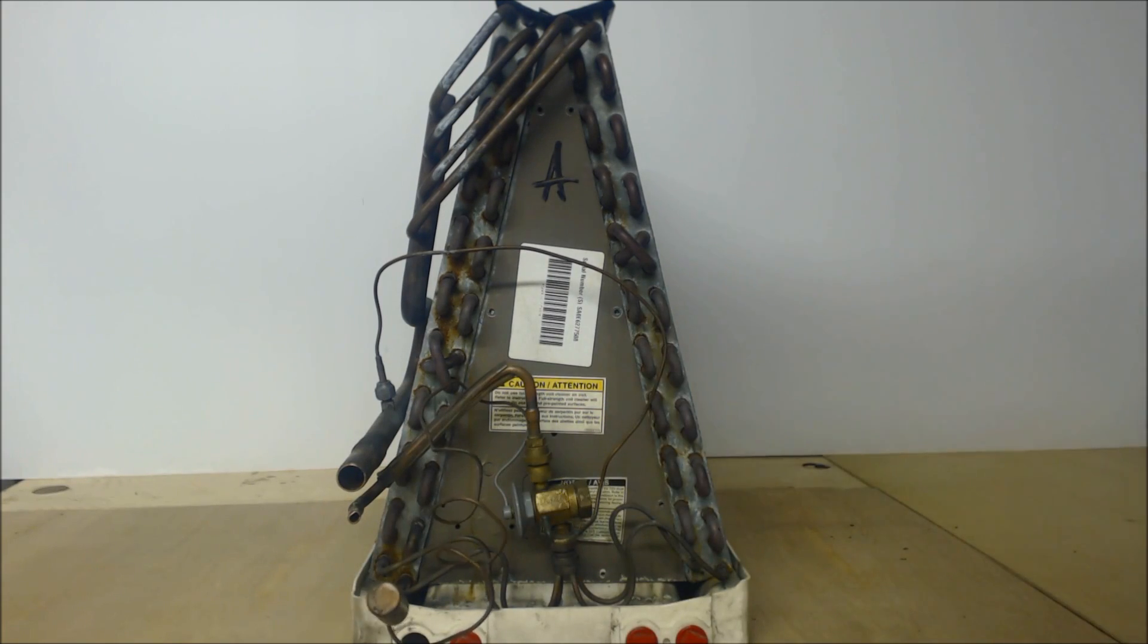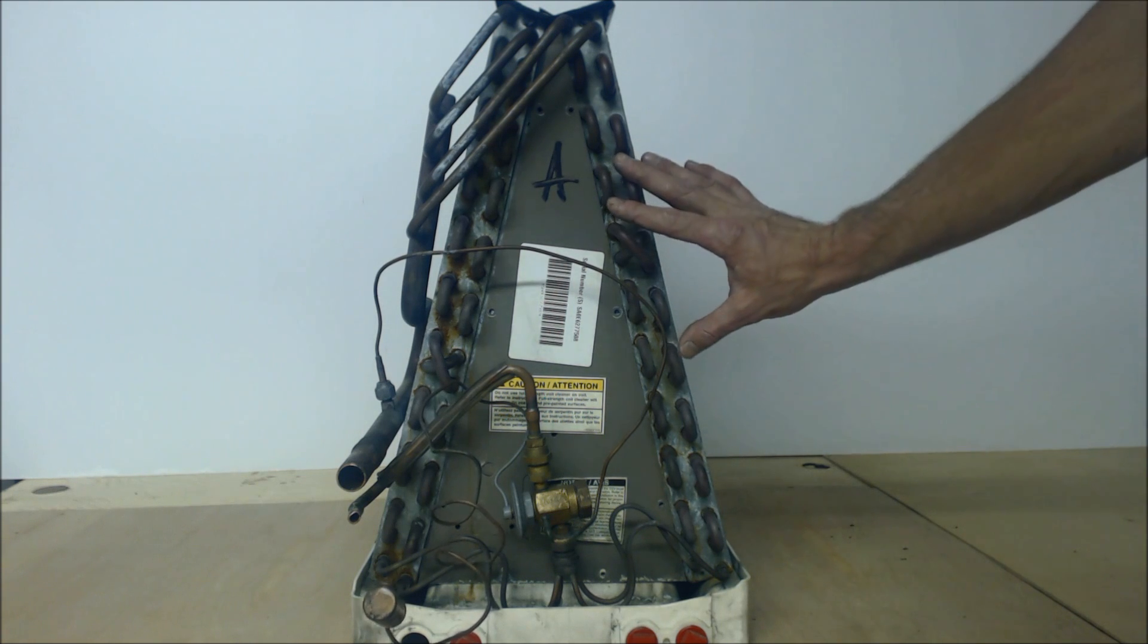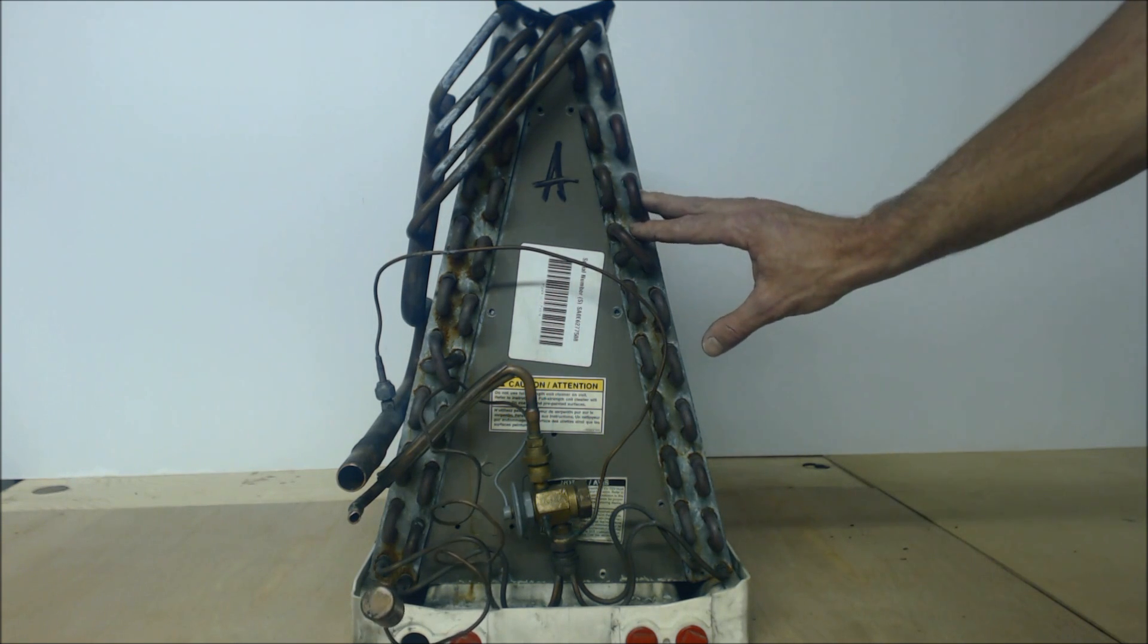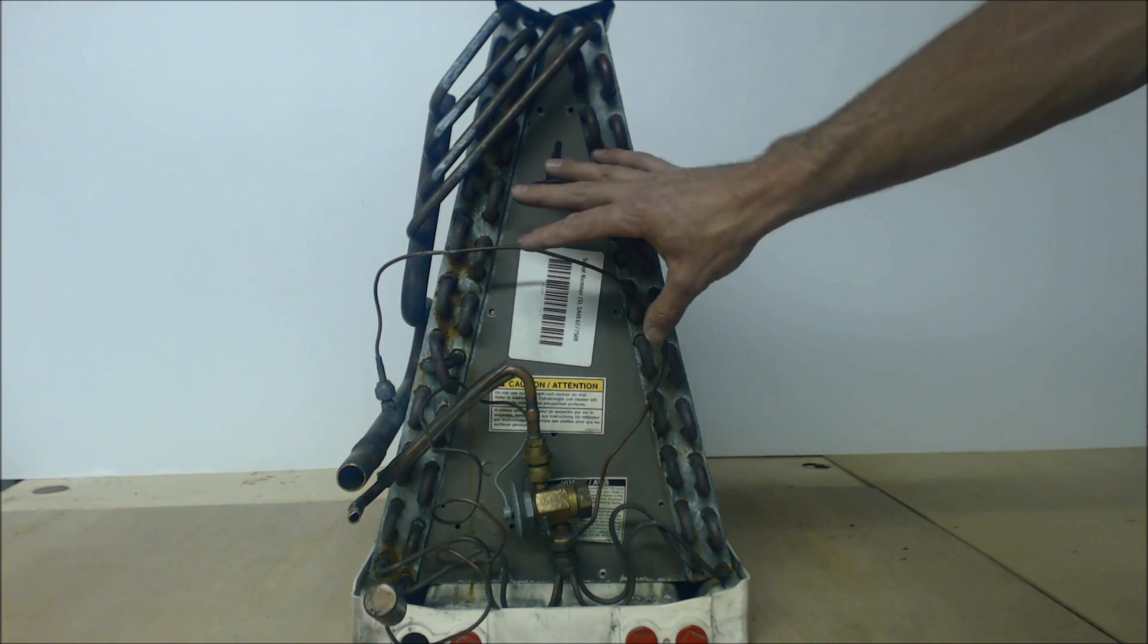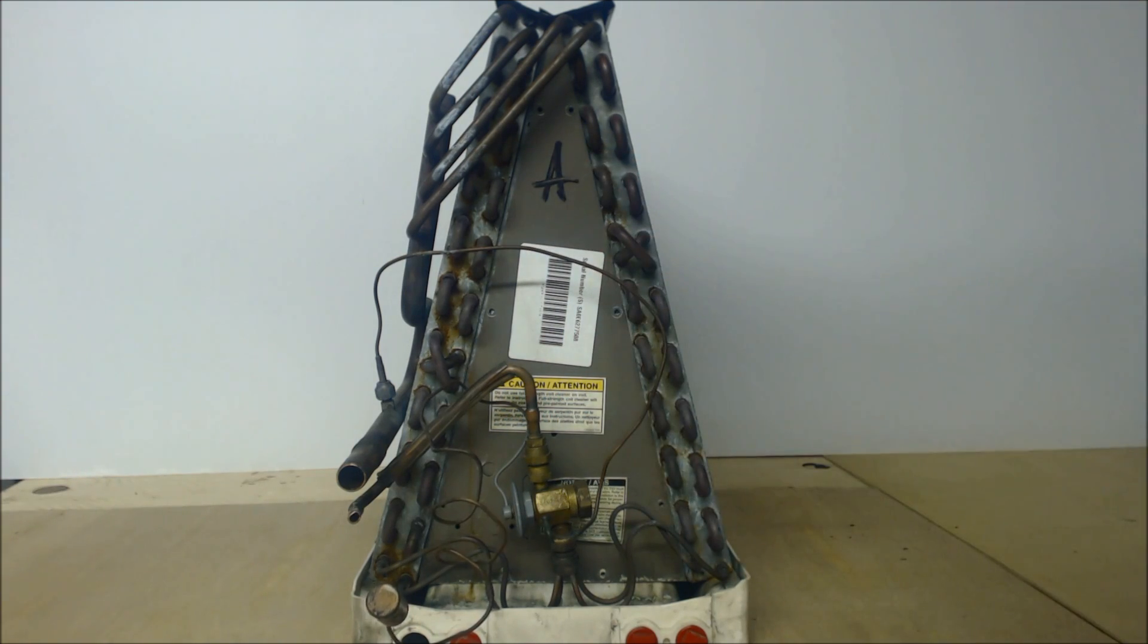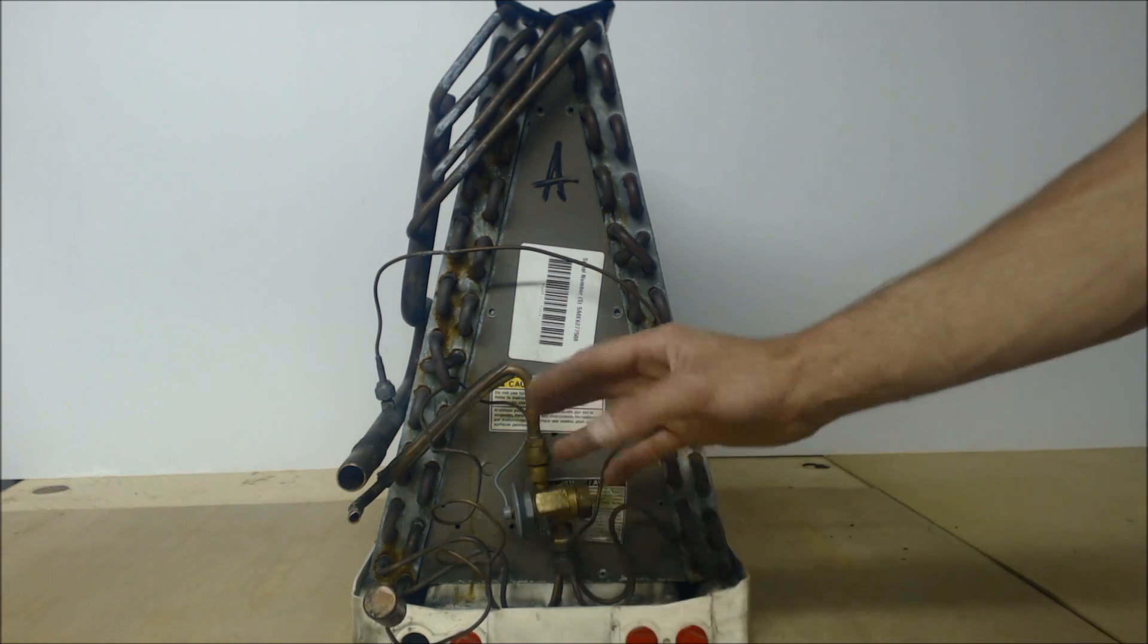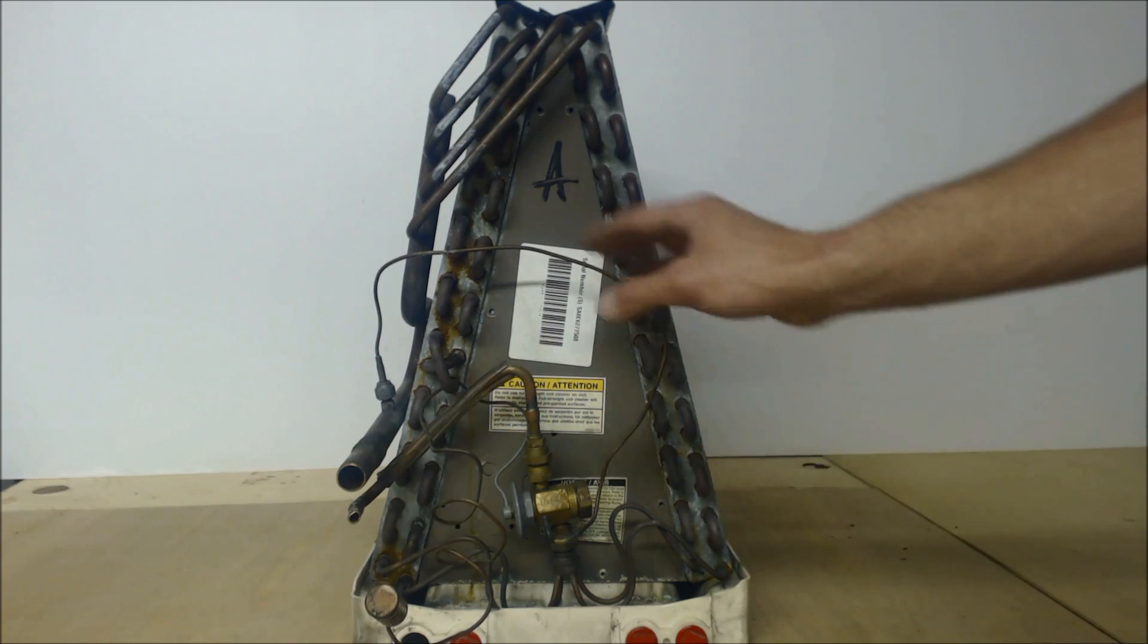It's absorbing heat from within the building. The evaporator coil is able to maintain temperature. If you don't have enough airflow across the evaporator coil, and your outdoor condensing unit is four ton and the TXV is four ton, it'll be feeding too much refrigerant into the coil.